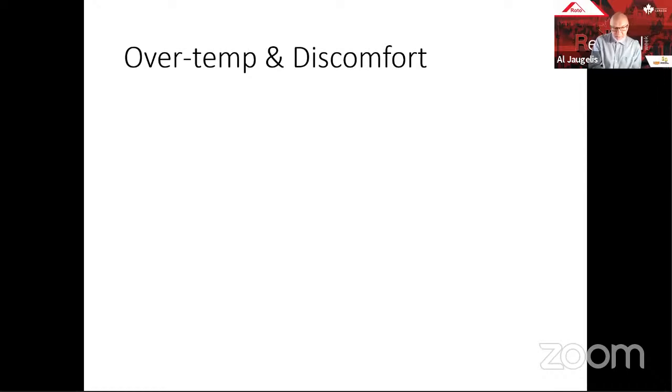So okay, please carry on, Jim. Yeah. Well, this is my last slide, Al, and this was the question. Actually, we led into this a little bit. In the analysis software programs, whether it's Hot 2000 or Energy Plus, which I'm using predominantly to generate some of these curves, you've got to be careful about whether it's doing MRT on long wave energy, or whether it's doing the short wave offsets. In most situations, I've had to develop an offline spreadsheet to take the hour by hour solar radiation and create a PPD, an offset directly to the predicted MRT for every hour.